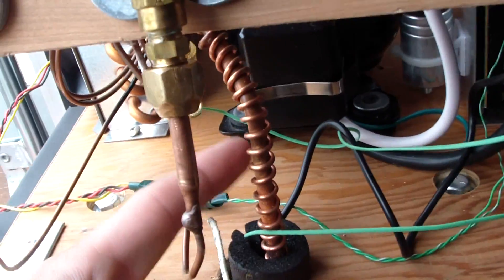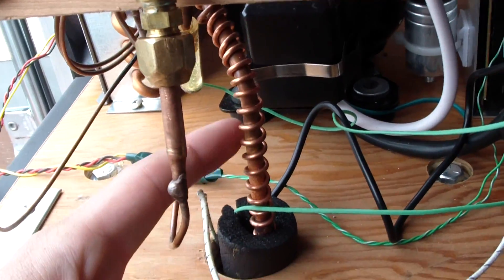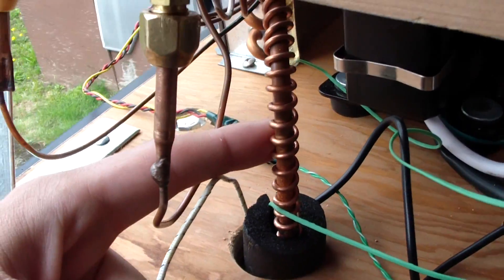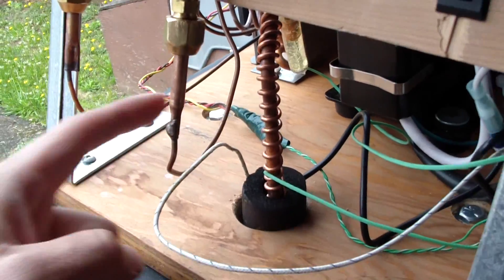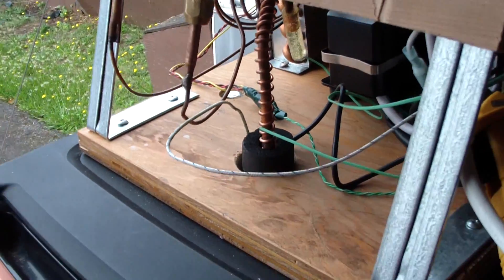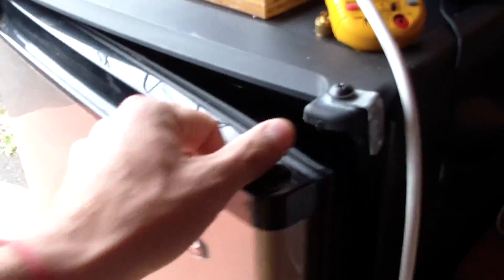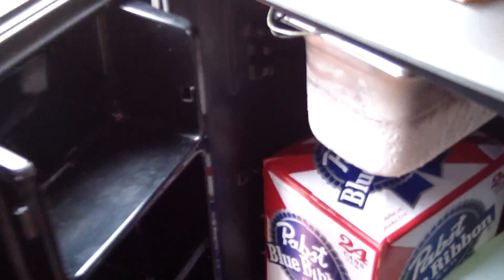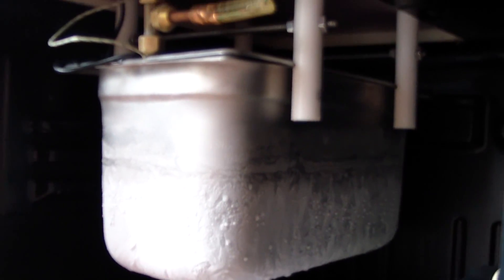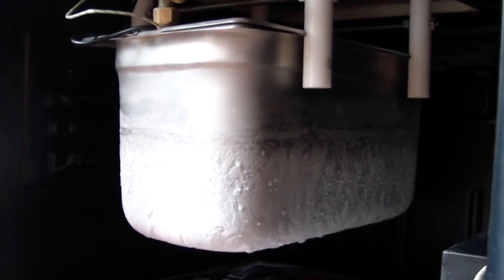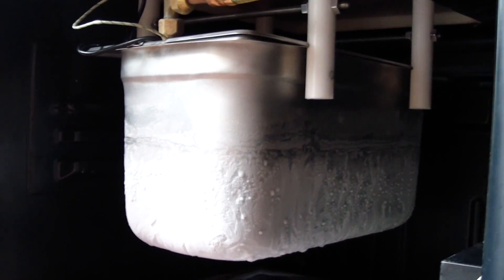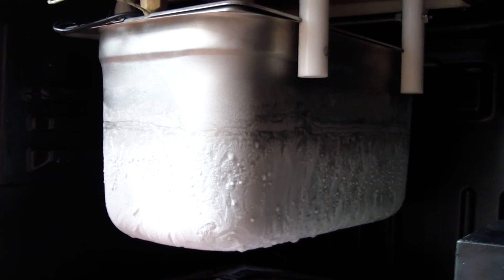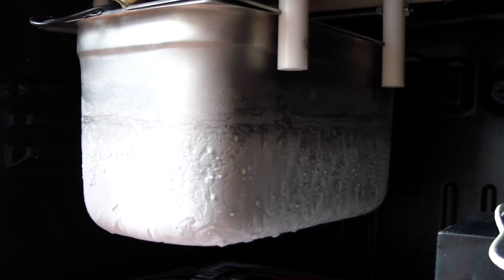We have a heat interchanger there. That large line in the middle is the suction line coming back from the evaporator. Small line is the capillary tube, the high pressure. Take a look here inside the unit. That's a brine tank there, a six inch third steam table pan that contains a solution of propylene glycol and water.